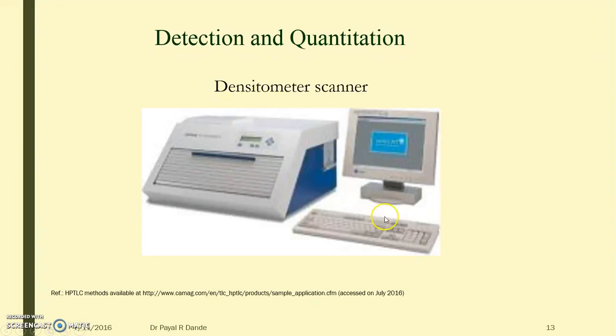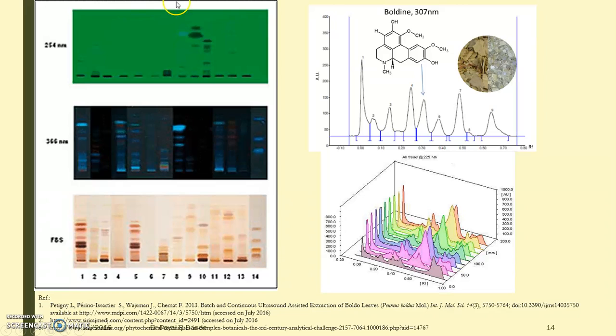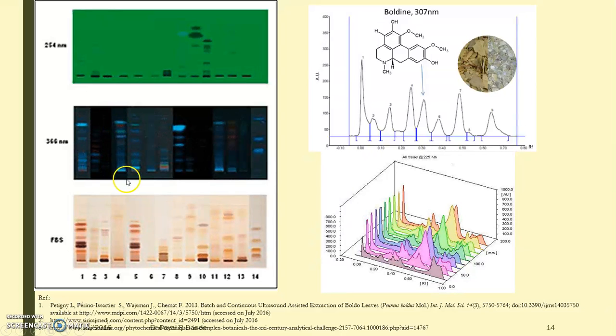The next important part of the instrument is the densitometer scanner. This is very important because it helps us to evaluate the chromatogram generated on the TLC plate. Once we have developed the chromatogram, we keep the TLC plate inside the scanner opening fixed, and then we can see and scan all the details on the software available on the desktop. The chromatogram is seen under UV light — we can evaluate our plate under 254 nanometer and 366 nanometer UV light, where we can see the different spots fluorescing.